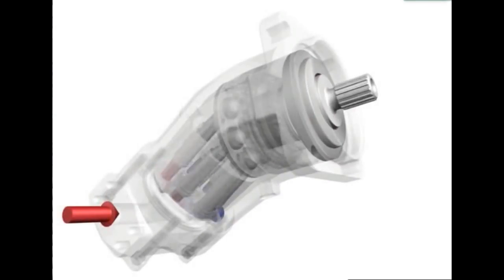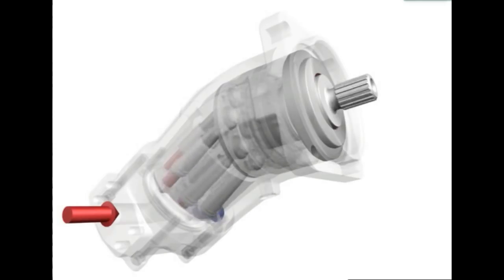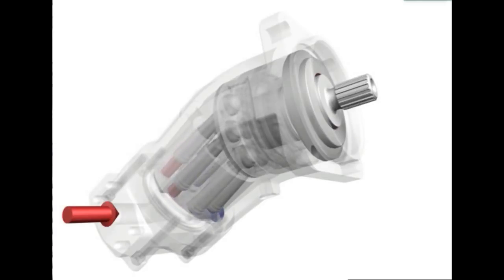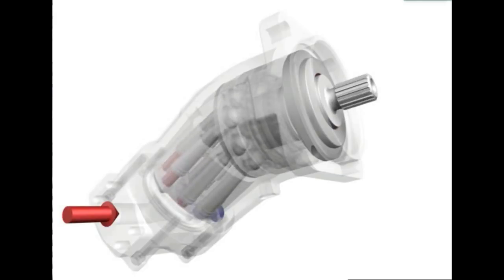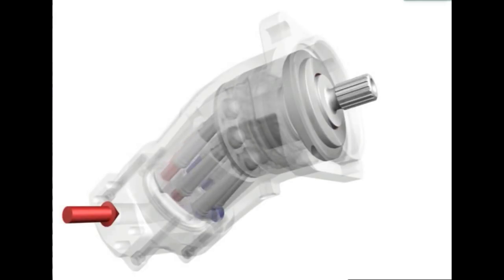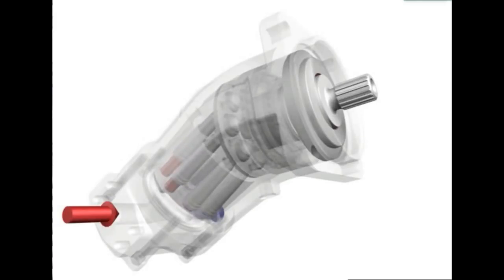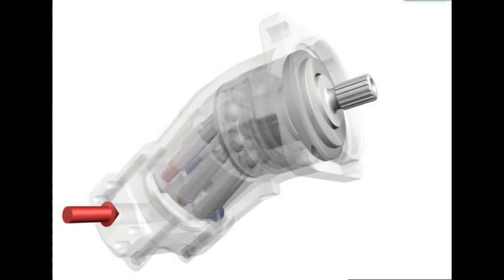Pressure against the end of these pistons creates force which acts at an angle to the output shaft. These pistons are pushed back in the barrel towards the output shaft. The result is an output torque which causes the output shaft, the pistons, and the barrel to rotate. The pistons over the outlet area are being forced into the barrel towards the control plate. Return oil from these pistons is forced through the other kidney-shaped opening and out the outlet port.